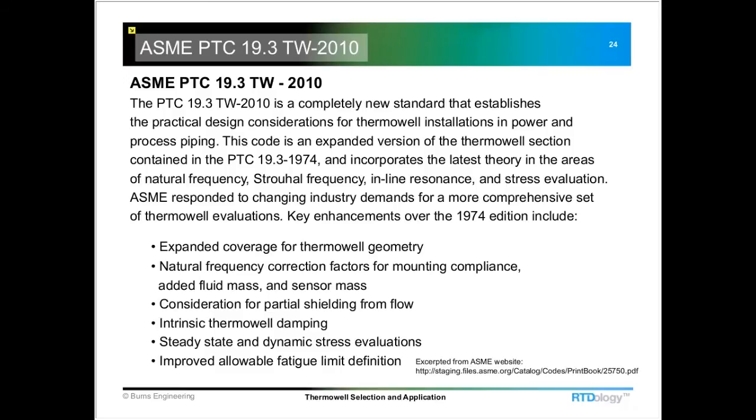And this is a little excerpt from the ASME website, and really the only reason I put this up here is just to demonstrate that it was updated in 2010, and it's quite different than the old standard, which had been around for decades. And it does a much better job of giving you an accurate picture of how that Thermowell is going to perform in your process.